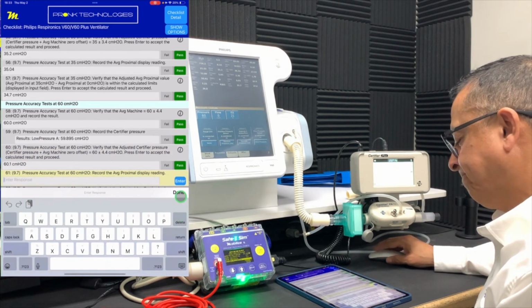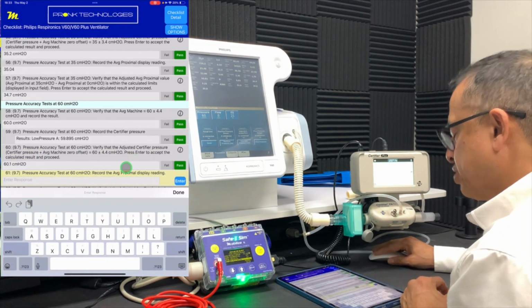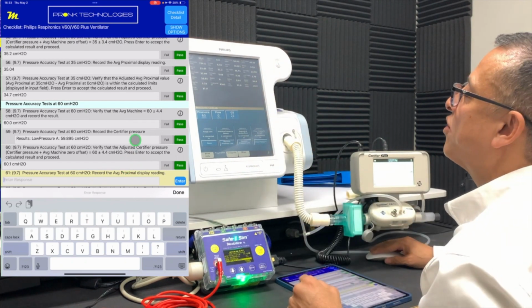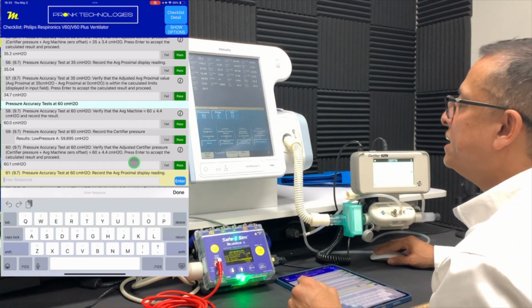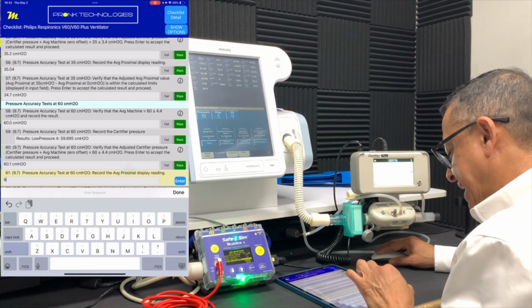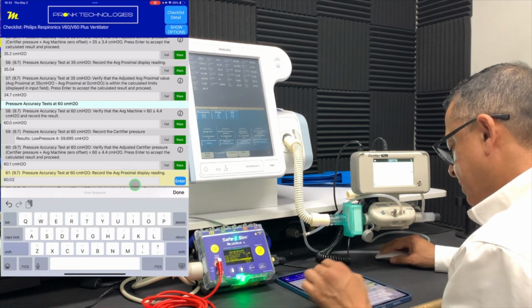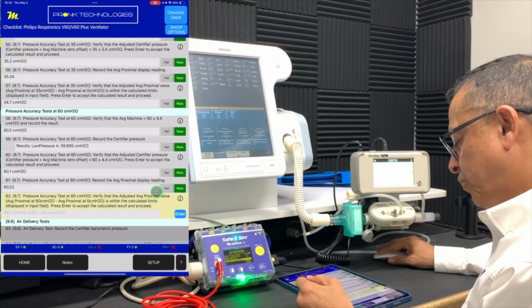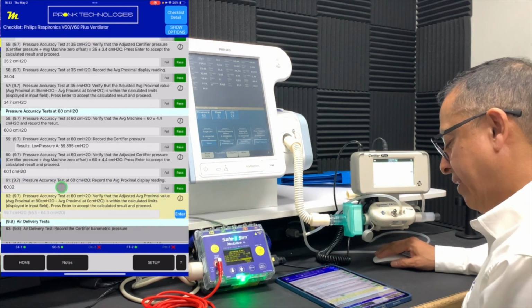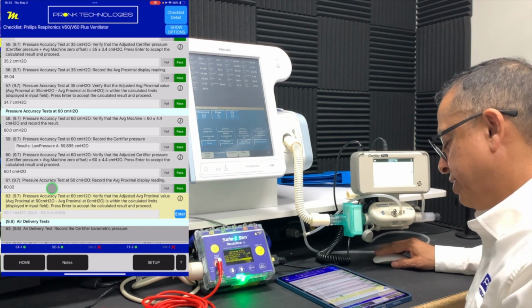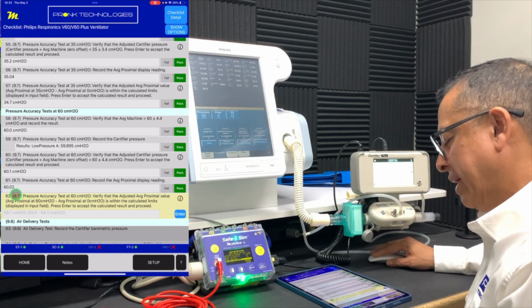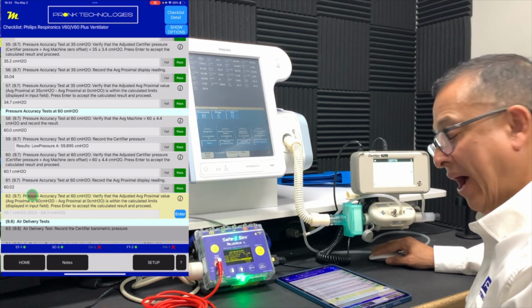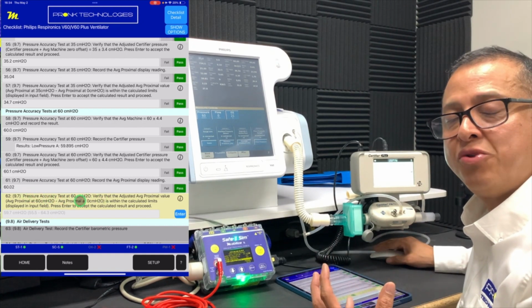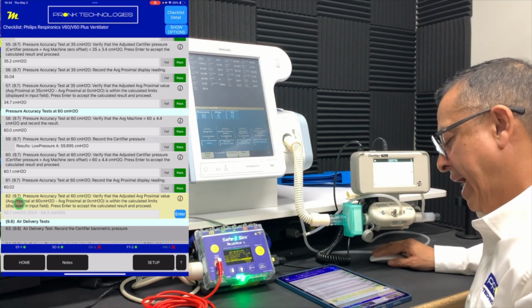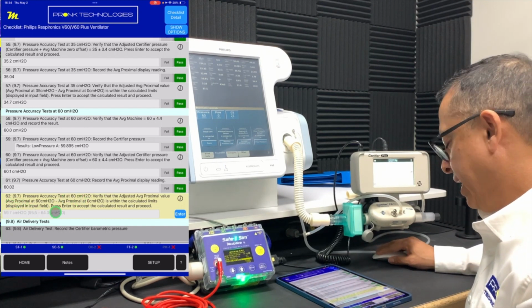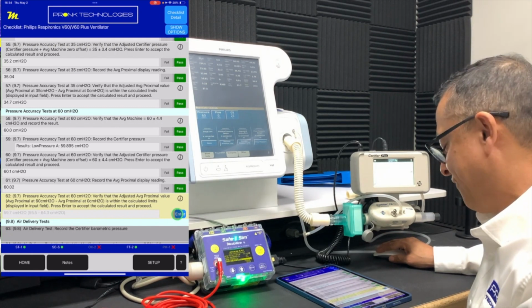We capture that result. Now we'll need to measure the average proximal display, and we'll observe that for a moment, get a good measurement. That looks like it's at 60.02. Capture that. And yet, one more calculation that has to be done at this 60 centimeters of water test. The formula is laid out in the procedure so you know what the calculation is based on. This is what's in the service manual itself. So we outline it there for you and then display that calculated value. It's within range, so you confirm it and accept that value.